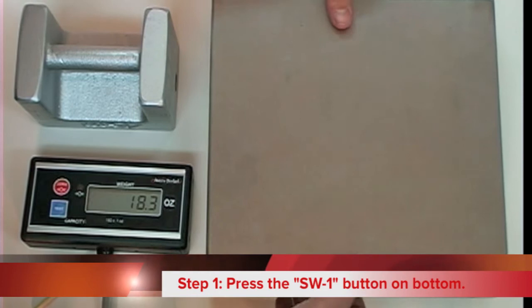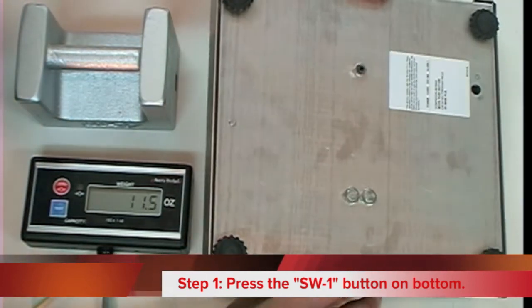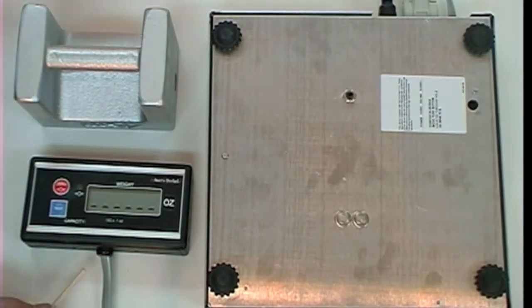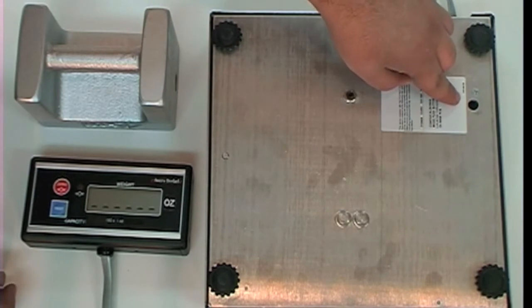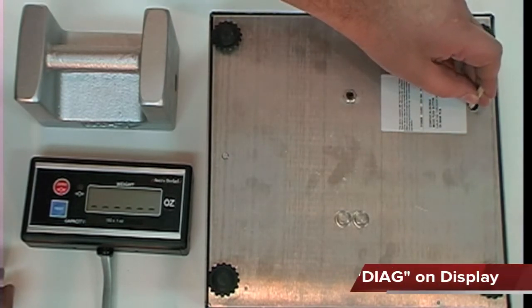To start, using a pen or small screwdriver, press the SW1 button located on the bottom of the scale. The display should read DIAG for Diagnose.